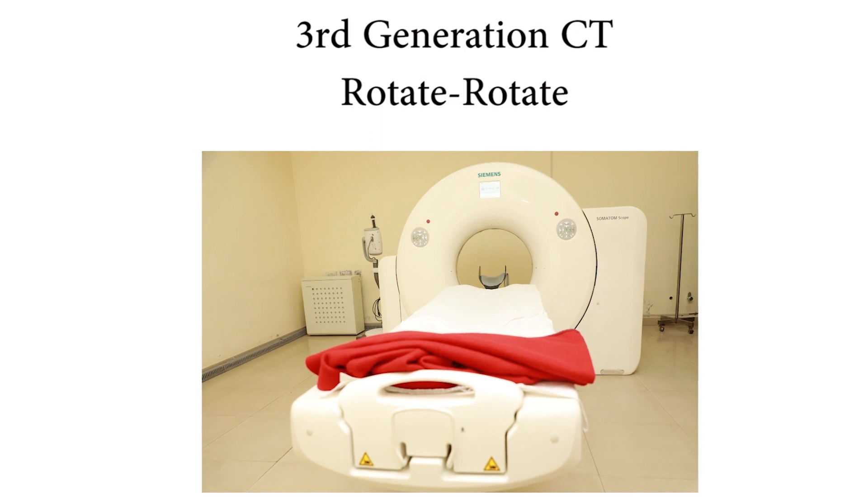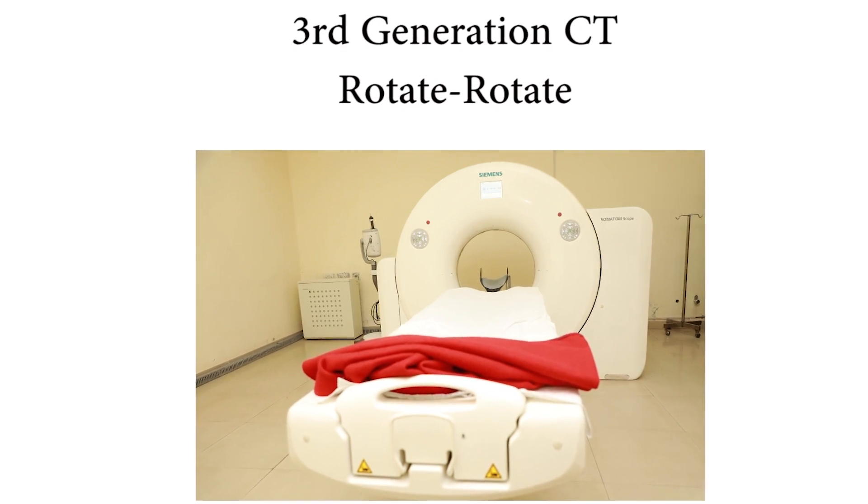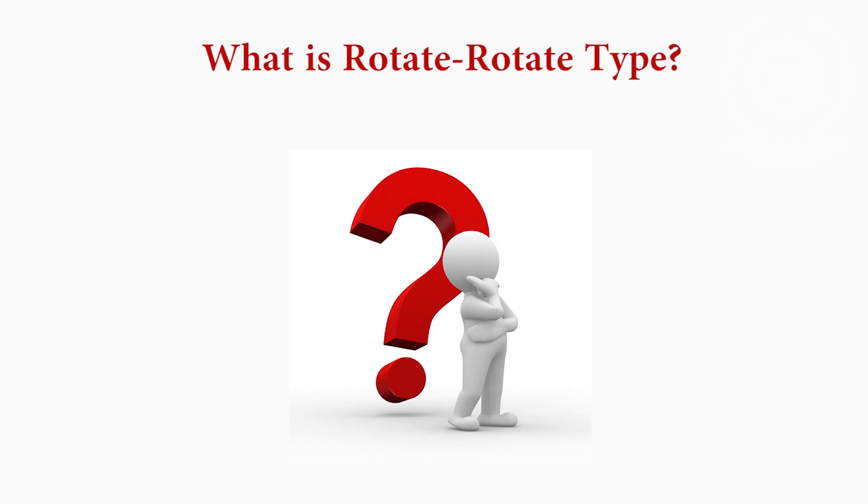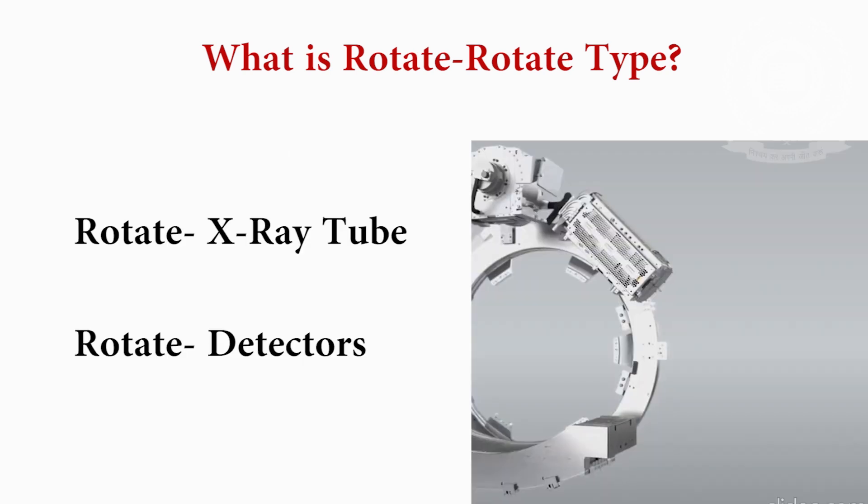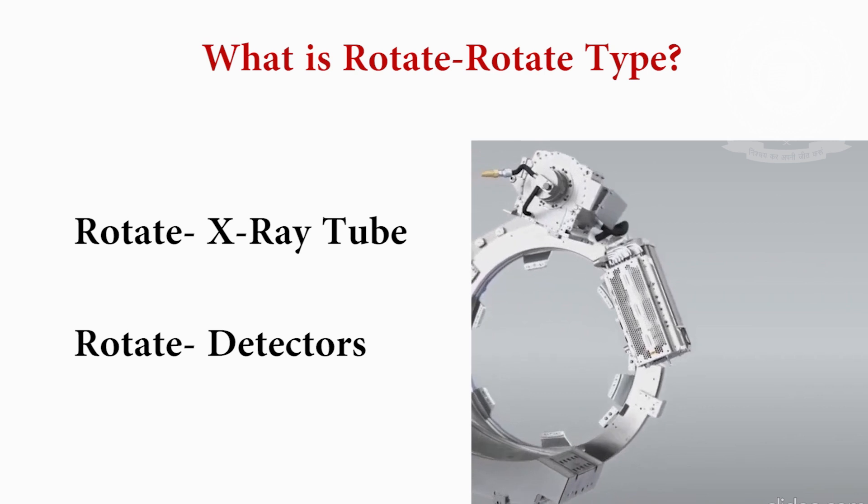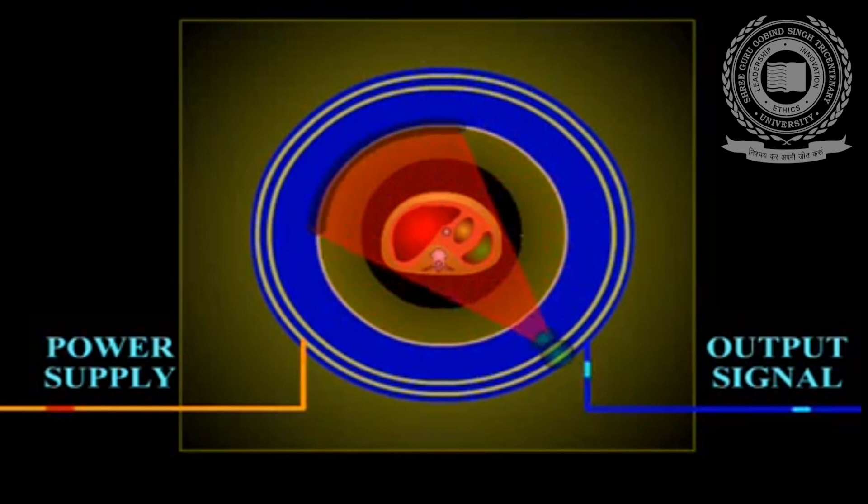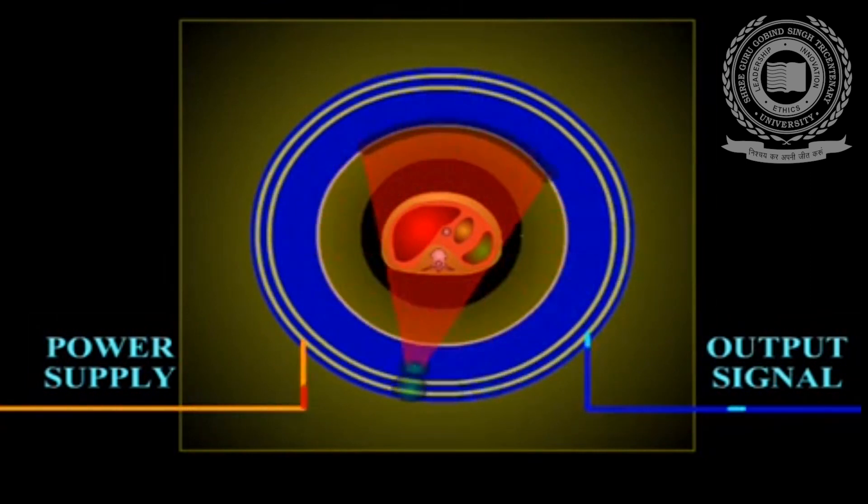And very soon third generation was introduced, third generation scanner known as rotate-rotate type. What is rotate-rotate type? Two time rotate word is used, one for X-ray tube and second for detectors. As you can see in this animation, the X-ray tube and detectors both rotate around the patient but parallel to each other.